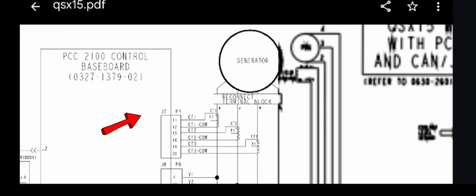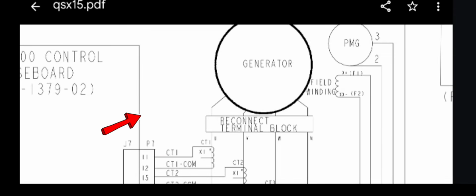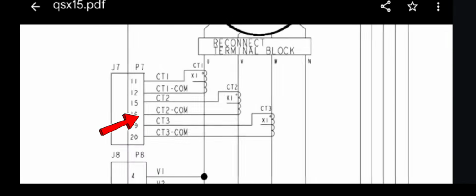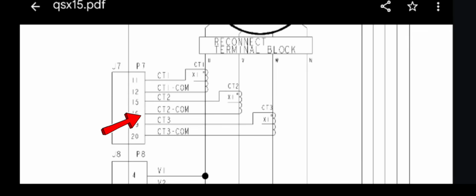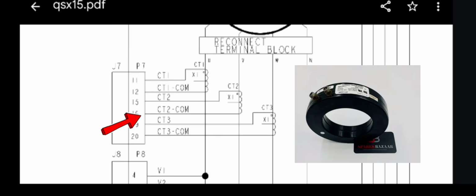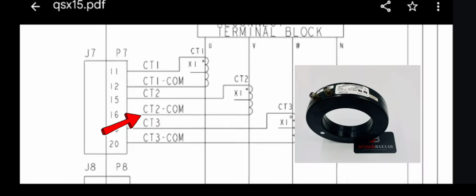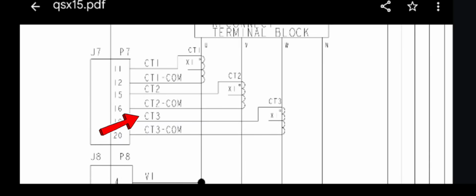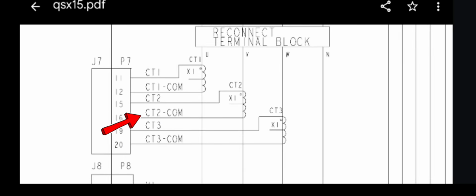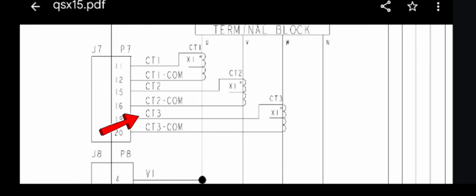And on the upper side, as you can see, this is our alternator. The alternator has three phases, and each phase has a CT coil, current transformer. Each current transformer has two wires: one common, one power. As you can see here, CT number one: power is in pin number 11, and common is in P7 connector pin number 12. And you can follow the same pattern.